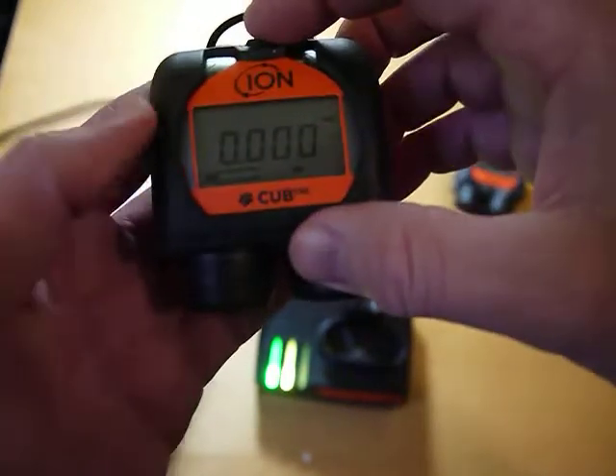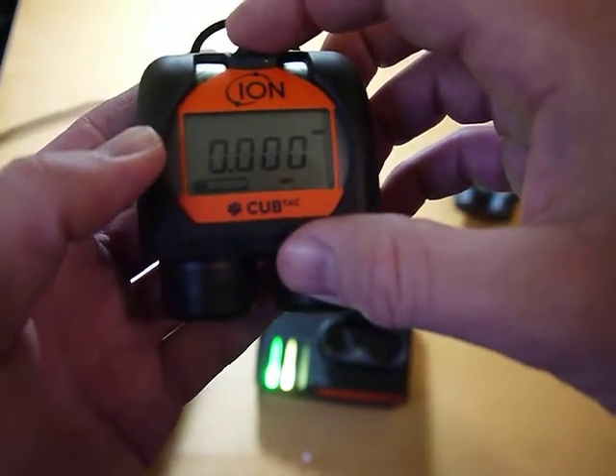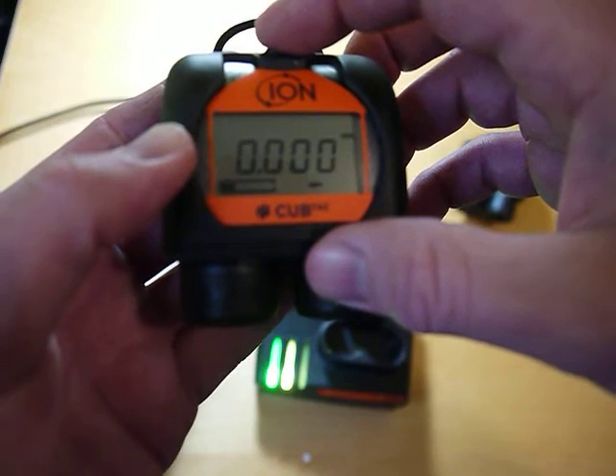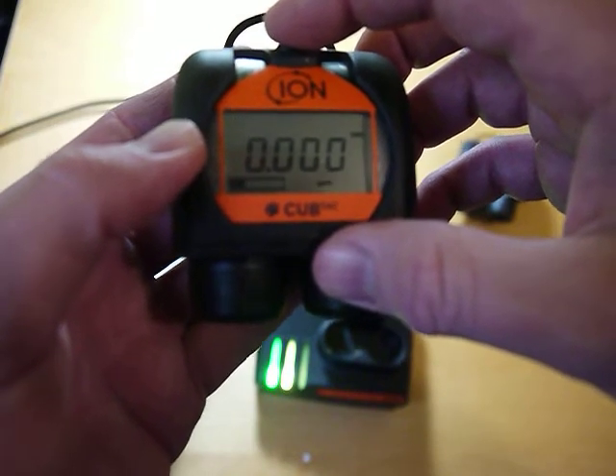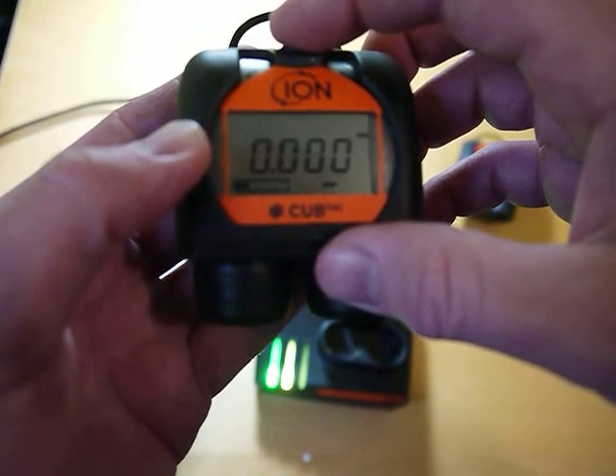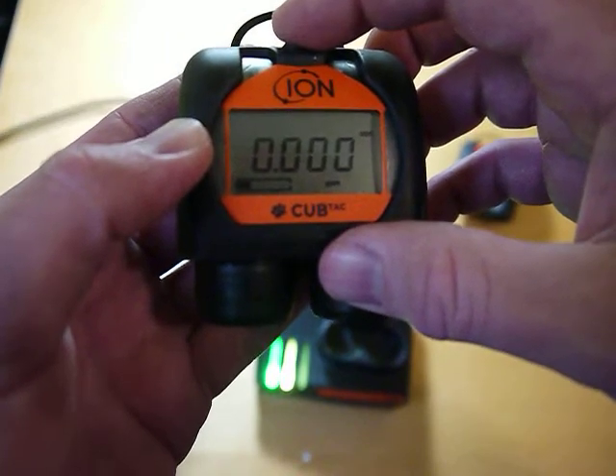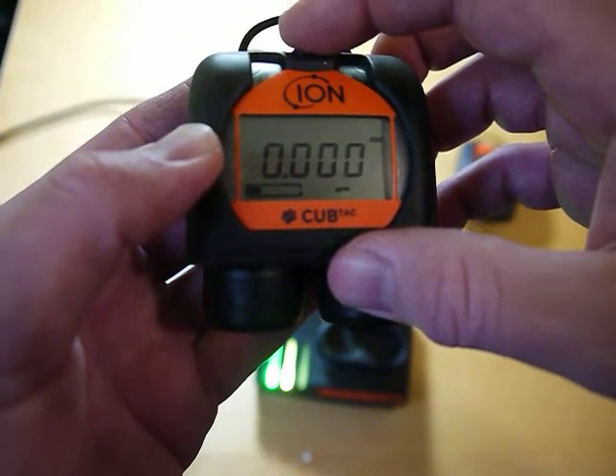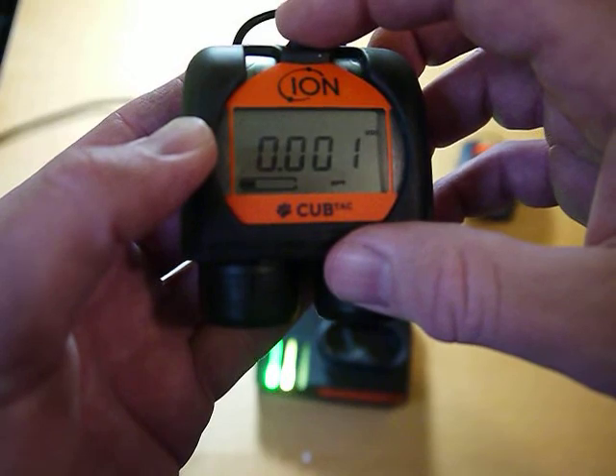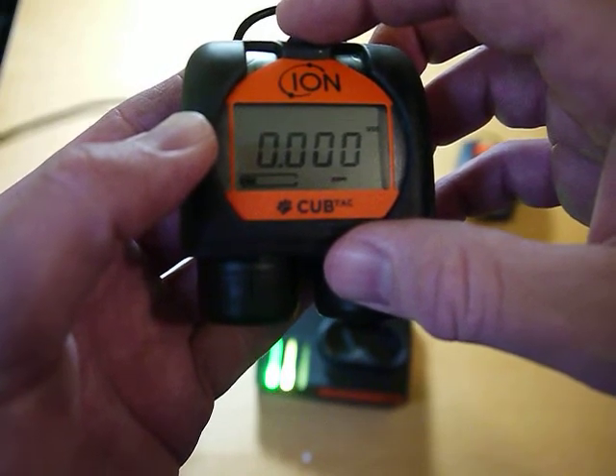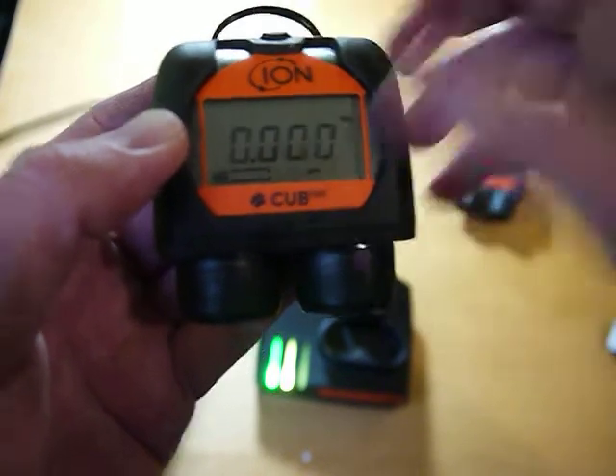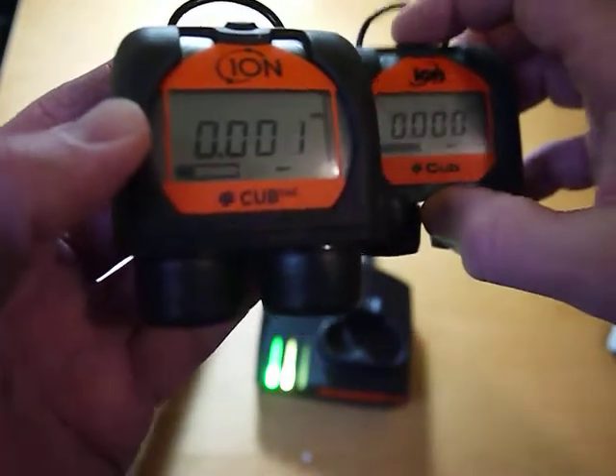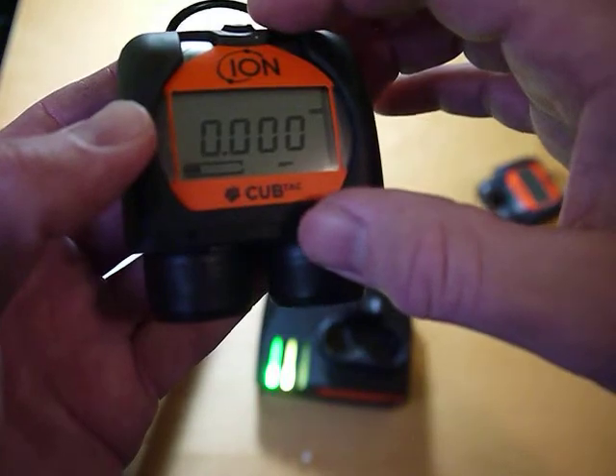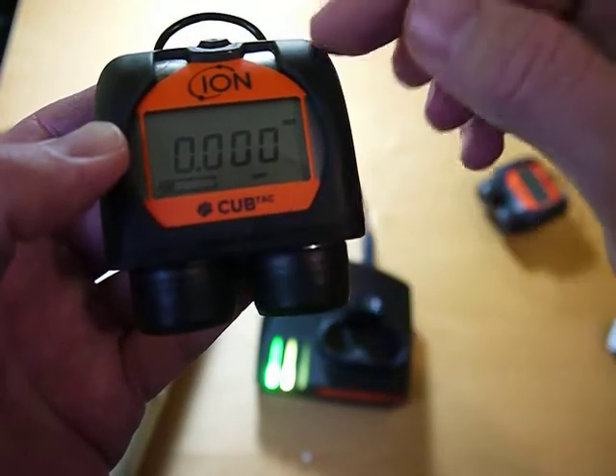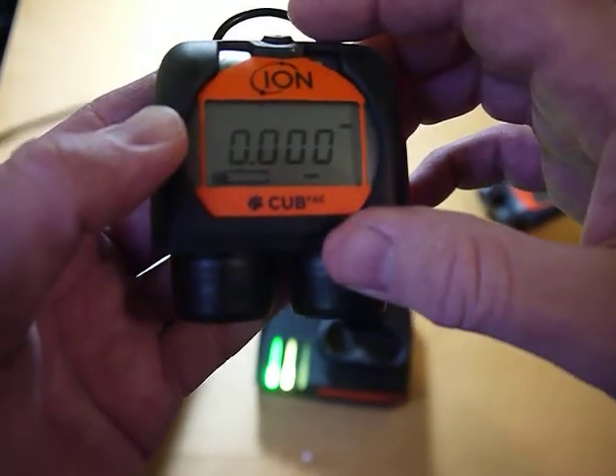The TAC mode has a 10.0 lamp. It's basically designed especially for refineries and places interested in benzene. The 10.6 electron volt lamp eliminates a lot of the other gases that have ionization potentials above 10, where this one has the 10.6 lamp. So basically you pick up more chemicals with this, but if you're worried about BTEX or benzene and stuff like that, this is a better unit for doing that type of monitoring.